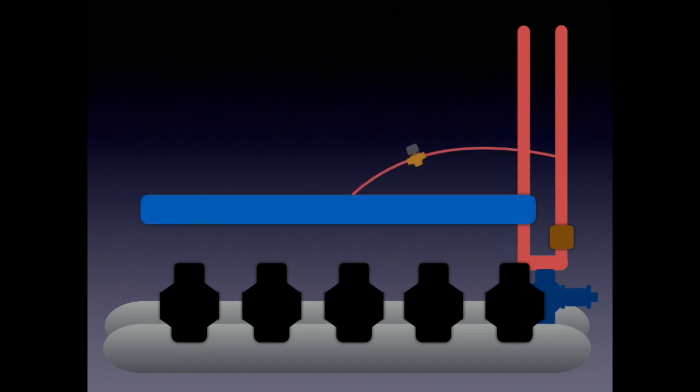Now back to this split condenser operation. When that split condenser solenoid shuts, another valve opens bleeding the remaining refrigerant in the unused condenser back into the suction header. Now on either side of this unused condenser, where I've had these brown boxes that I think you guys have noticed.